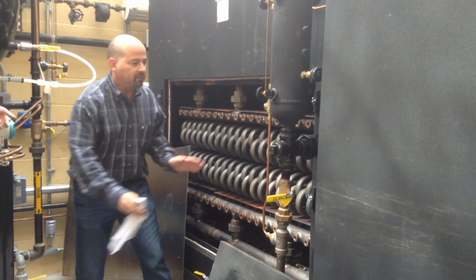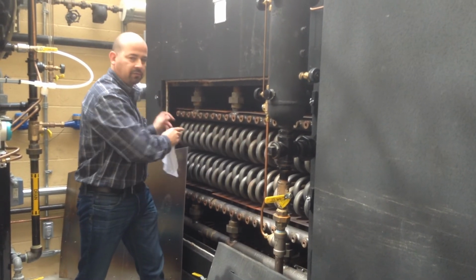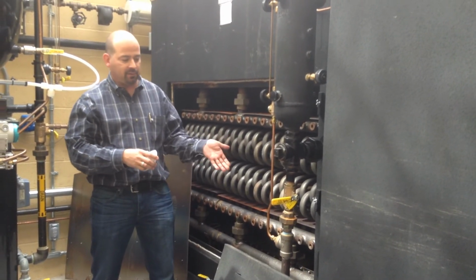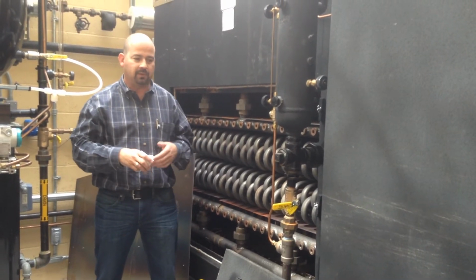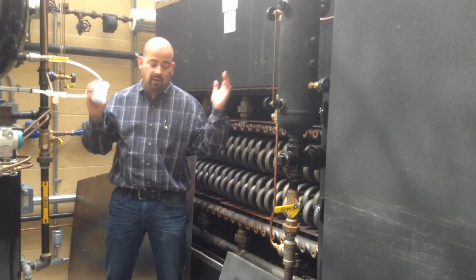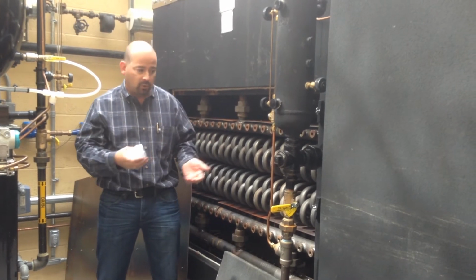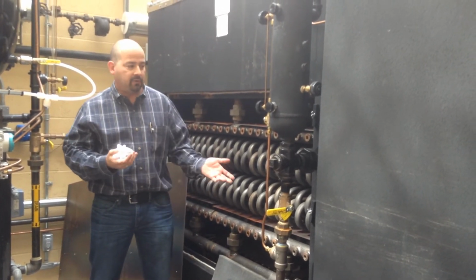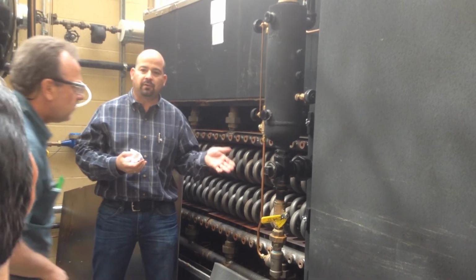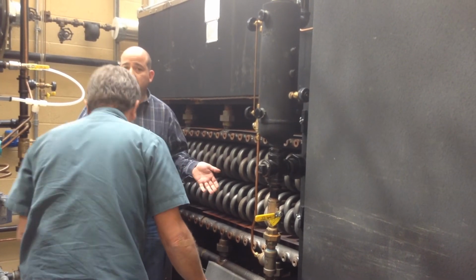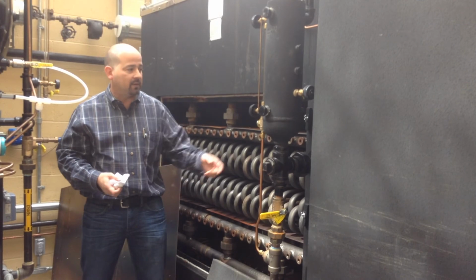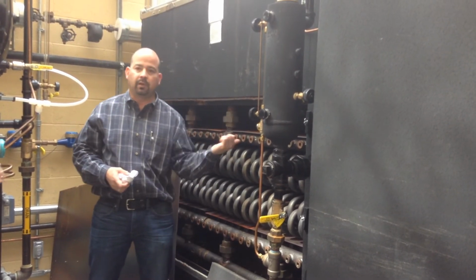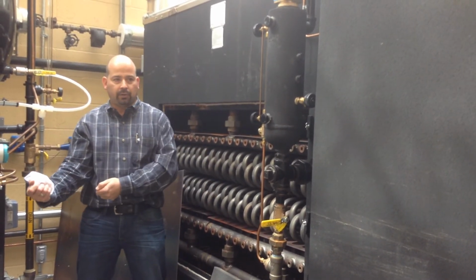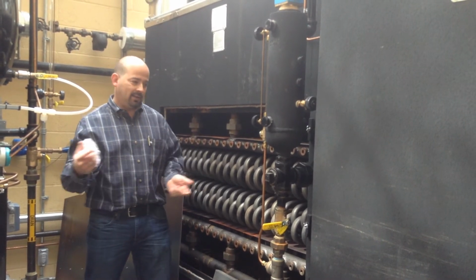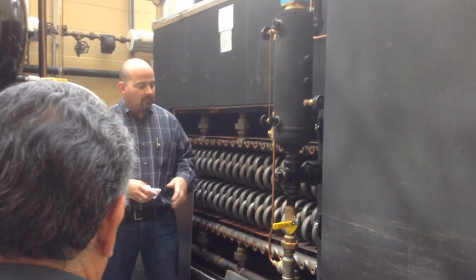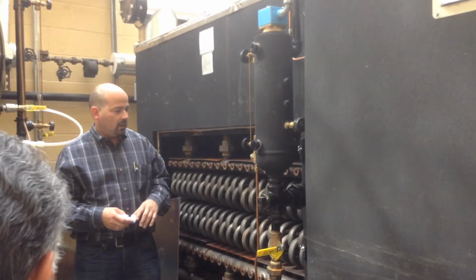So these are tube bundles. You got 1, 2, 3 tube bundles. If you ever had to retube the boiler, which hopefully you don't ever have to, but like let's say the water chemistry went wacky, somebody wasn't blowing down the boiler, that kind of thing, then you might lose a tube bundle. The good thing about this boiler is you don't have to do any welding, you don't have to do any specialized rolling, you don't have to do anything. You break a union here, break a union there, break a union on the other side, slide out the bundle, I make it sound easy but it's heavy, and then put in the new one, line it up, that's a bundle. We always stock these bundles.